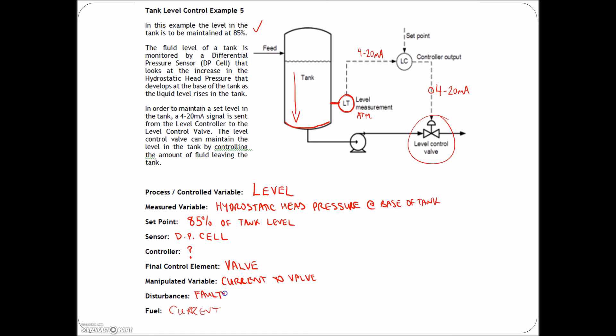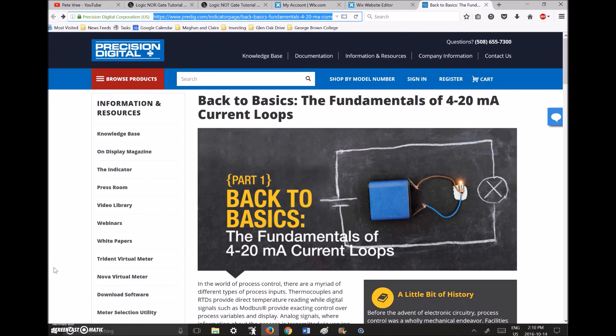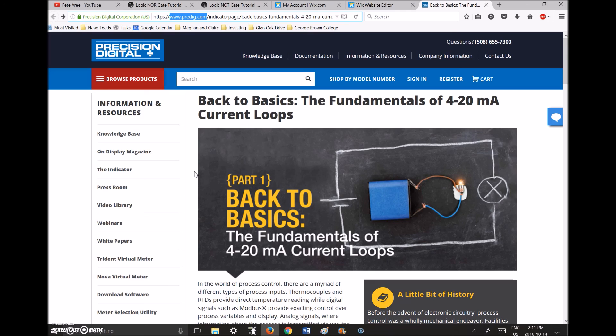Disturbances: anything we haven't put a sensor in to look at — for this one we'll just say a faulty valve. That's all for loop diagrams. Next we need to talk about the signal going from the sensor back to the controller — the sensor ties into a transmitter which sends a standardized signal back to the controller, normally 4 to 20 milliamps or 0 to 5 volts DC. There's a great resource at www.predig.com with white papers on these topics — I'll put the link below. Next video we'll start talking about 4 to 20 milliamp currents.